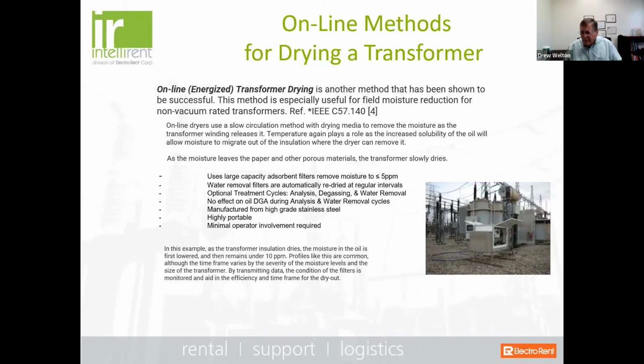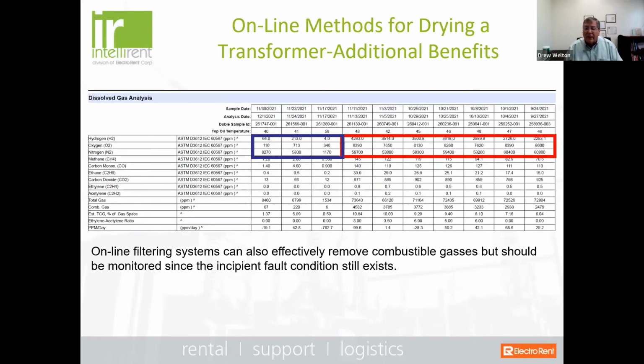Okay, so one of the other benefits of using a system like this is it will actually perform a degassing as well. So, two separate problems that we can have in transformers: we can have excessive levels of gassing due to various conditions, or a moisture problem. Now, what's important to know is that if you do want to go through a degassing cycle in the transformer, it's very, very important to know what is causing that gassing condition. So, if we have fixed an issue or repaired a problem and you still have a high level of gas in your transformer oil, a unit such as this can remove the gas.